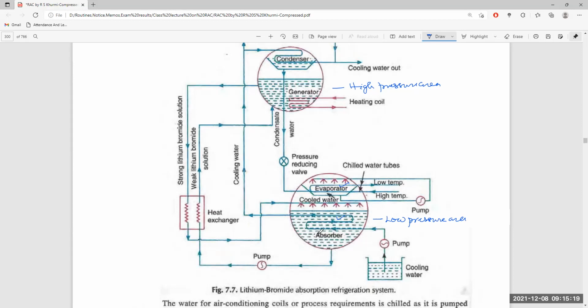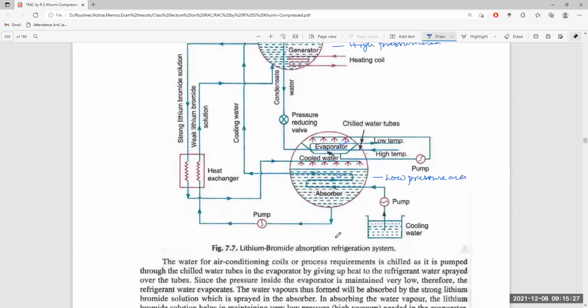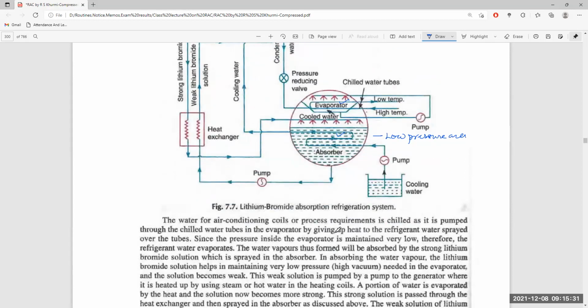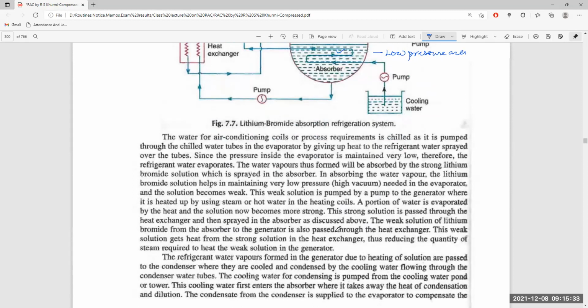So this portion is being carried here. This is carrying out from here. The exchanger heat, then again sprayed here, and then it absorbs the water. Absorbed water then again moves. This strong solution, this weak solution of lithium bromide from the absorber to the generator is also passed through the heat exchanger. This weak solution gets heat from the strong solution, thus reducing the quantity of steam required to heat the weak solution in the generator.